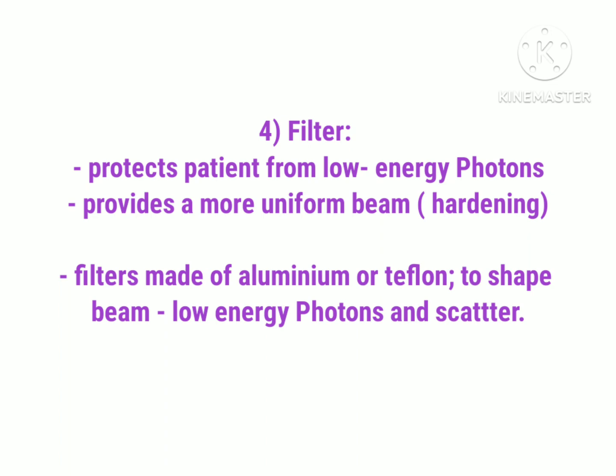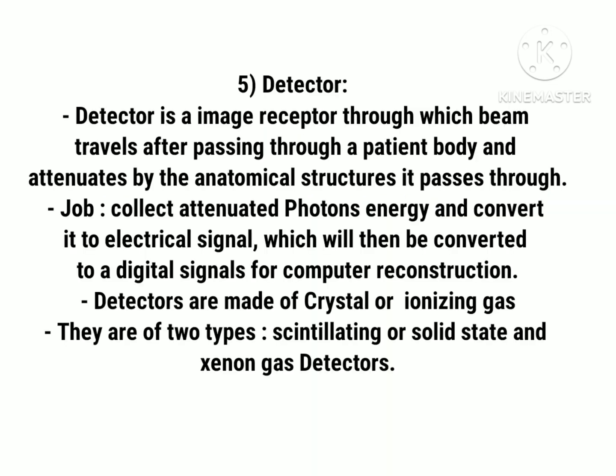The fourth component of the gantry is the filter, which protects the patient from low energy photons and provides a more uniform beam — meaning it hardens the x-ray beam. The filters are made up of either aluminium or Teflon so that they can shape the x-ray beam.